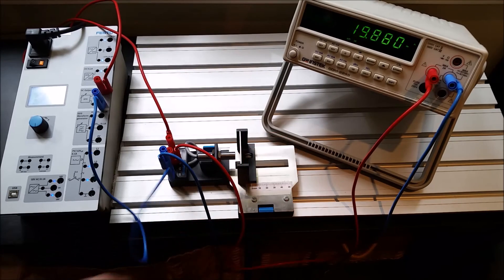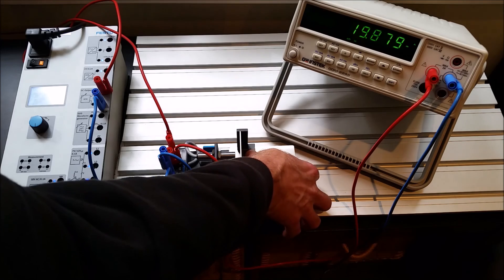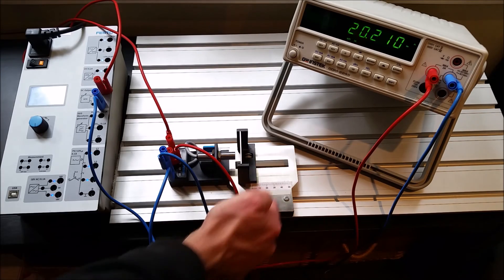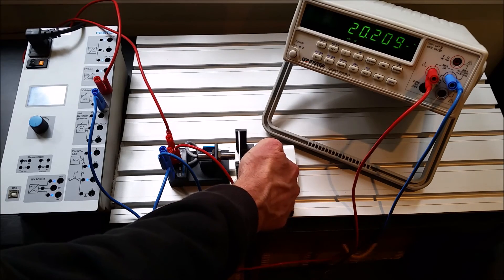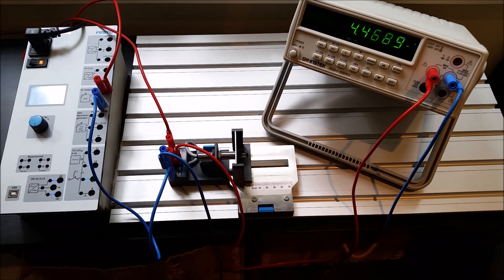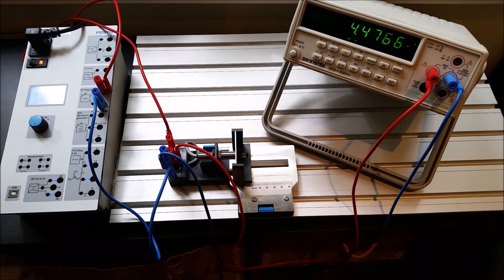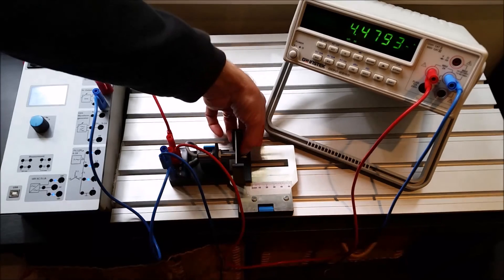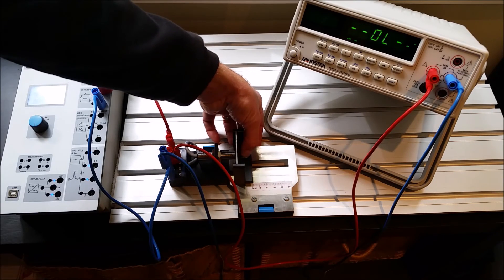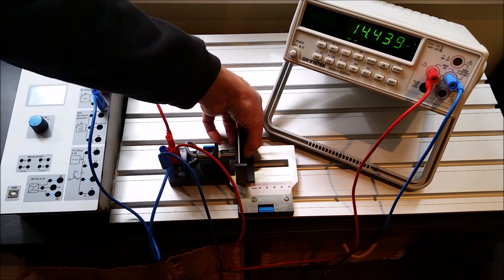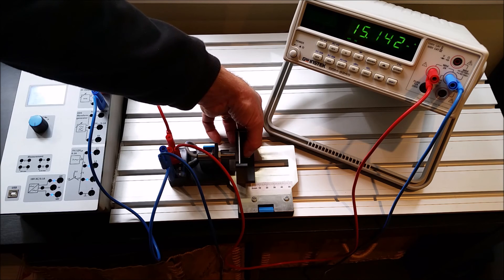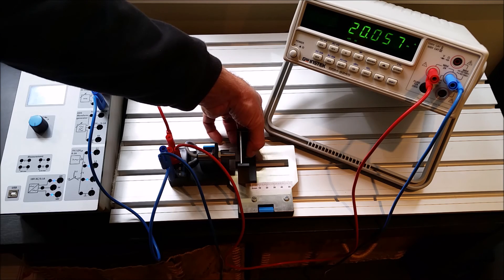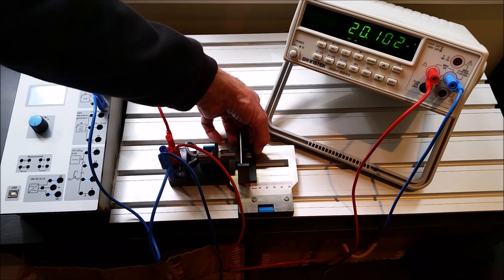This is my 6 mils, and I'm getting 20 milliamps. And if I push this all the way in, there's my 0, there's my 4, roughly 4. It's not exactly 4, but there's my 4 milliamps. So you can see here as I go from 0 to 6 mils, I'm getting my 4 to 20 milliamps of current.